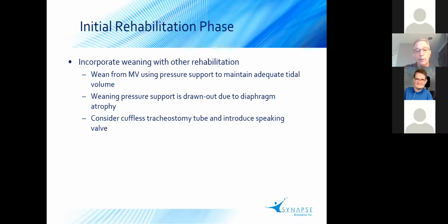So if you've got a patient that's been on mechanical ventilation 45, 60 days, you've got a lot of diaphragm conditioning to do. So just understand that for some of these folks, it's going to be a drawn out process. It's not going to be a quick transition from the ventilator to diaphragm pacing, but they will get there. And again, when you get them to the point where they're on CPAP or trach collar trials, those are the times to consider a cuffless tracheostomy tube and introduce a speaking valve.